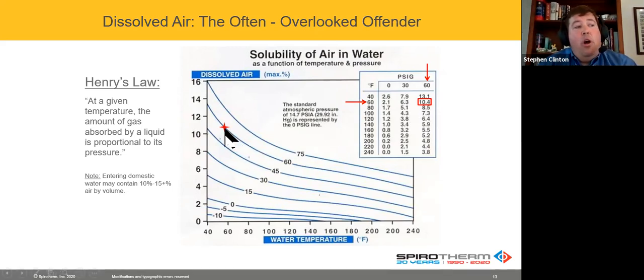However, let's say we take that water and we don't change the pressure at all. All we do is we heat it up to 180 degrees. Well, I'm going to go to my cheat sheet here, it drops down to 5.2%. So what's happening is that fluid physically cannot hold air in solution. So oftentimes if we think about heating hot water systems that typically clog up and get dirty and tear up equipment, oftentimes that's because all that air comes out of the solution, gets pushed around, gets pushed back into solution when it hits the pump. We'll talk some more about that in a bit.